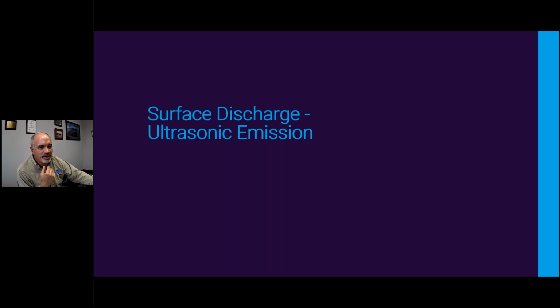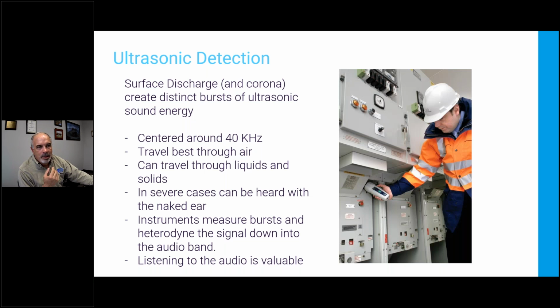I'm going to start with surface discharge because it's the most common, it's the fastest moving, it's easiest to find, but it's also the most likely cause of failure. So we're going to monitor it centered around 40 kilohertz. These waveforms are kind of broadband. They go from 30 to 50 kilohertz rather, and 40 kilohertz is just a convenient point for us.